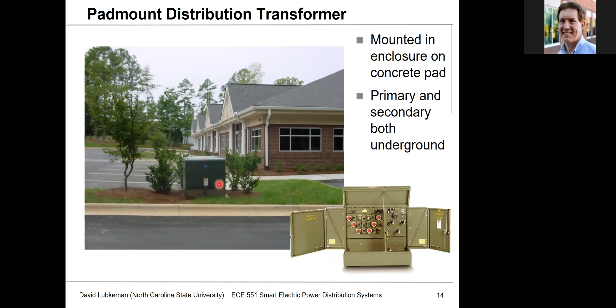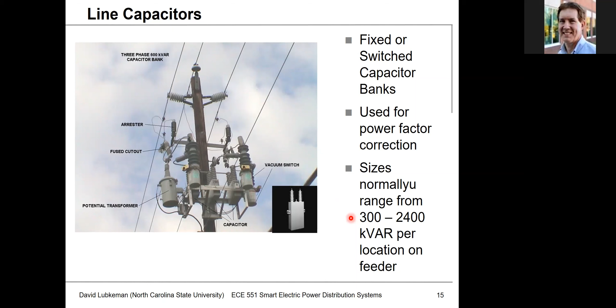For line capacitors, the line capacitors that we're going to use are basically in the format of a can. We'll talk later on about how we would make these devices, but you would mount these up on the pole, and if you wanted to have these be switchable, then you would typically nowadays have vacuum switches. These used to be oil switches, and associated with the control, you can open and close these capacitors, where the sizes would range maybe between 300 and 2400 kVAR for each location.